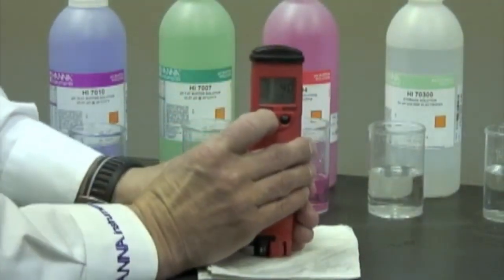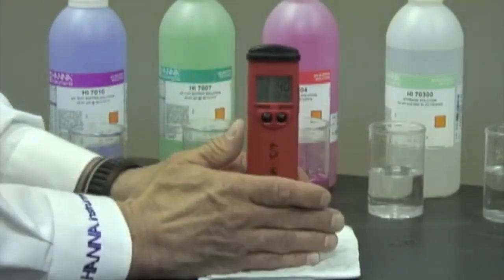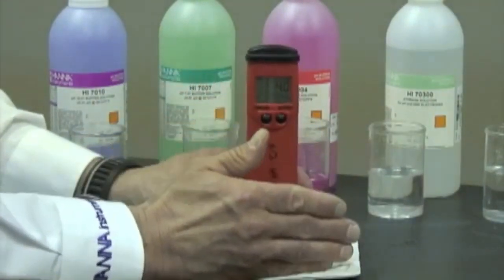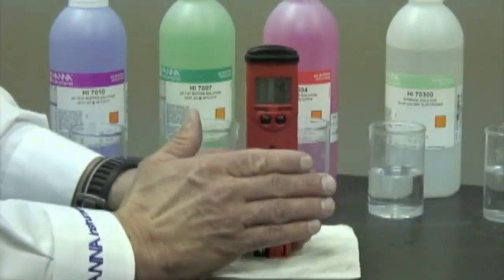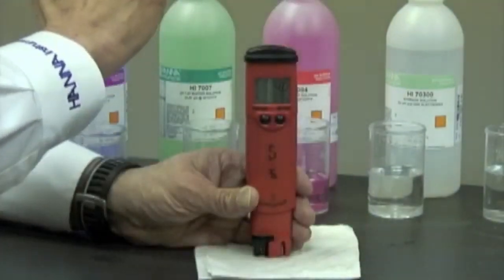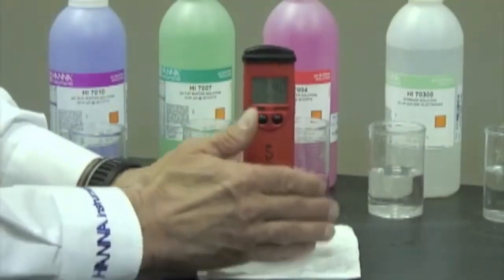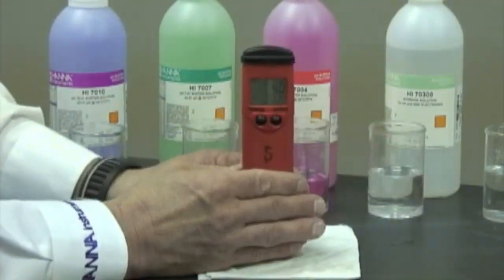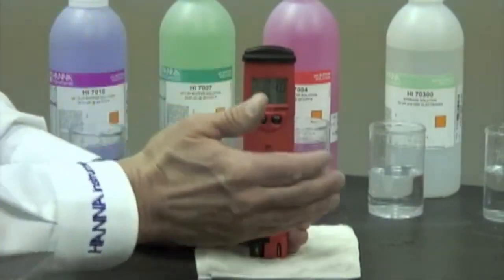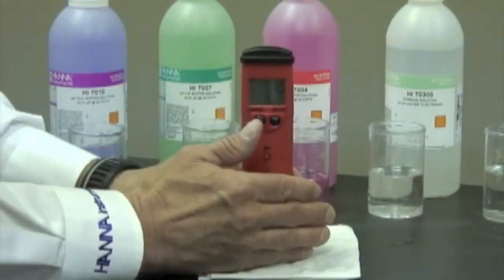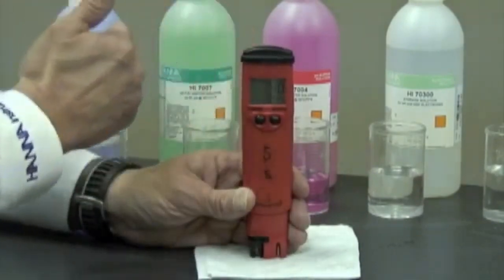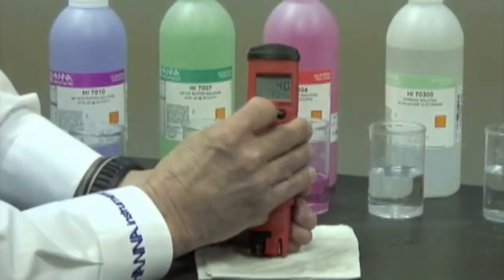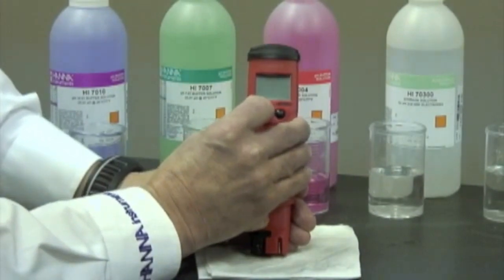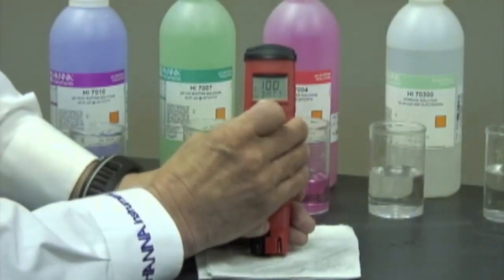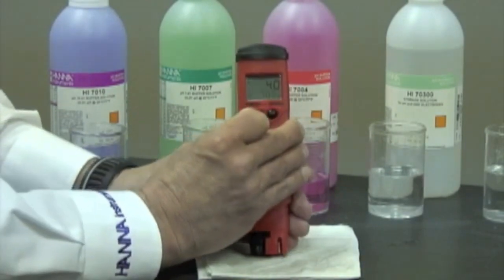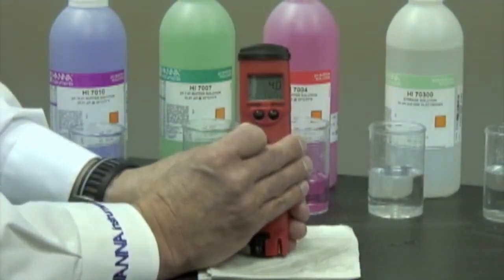Now it's important to note that you can either do a 1-point calibration, so if you're done calibrating at number 7 and that's good enough, then you can go back into the escape mode and go into measurement and measure the pH of whatever solution you're measuring. Or if you want to do a 2-point, depends on whether or not you're measuring an acid or a base or preference, then you can go into number 4 or number 10. It doesn't really matter. So in this case, I'm going to turn the meter off, turn it back on, go into the measurement mode. My meter is now calibrated and ready for use.